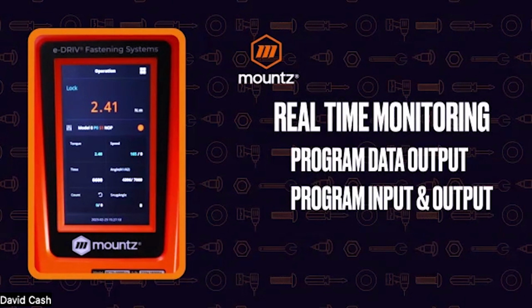But if we want to also send the data happening from the tool itself, that would be a time date stamp of the torque, or the preset that was used, the actual outcome of that, how long it took to run down in milliseconds, what was the amount of angle or turn that happened, whether there was an error, and if so, what the error code was. All of that information can be sent out of the controller, or it can be saved locally.